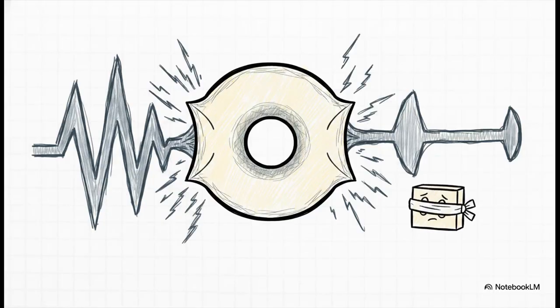And here is exactly why that physics lesson matters for our relays. CT saturation. When that massive DC offset heavy fault current hits the current transformer, it can completely overwhelm the CT's internal iron core. The core physically can't contain any more magnetic flux, so it saturates. The output waveform sent to the relay distorts and flattens out, so your relay ends up getting false, understated current readings exactly when it needs absolute accuracy the most.